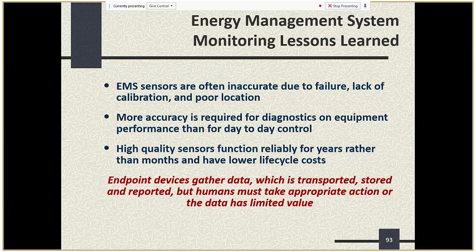Go to slide 94. Yeah, Dave, if I could inject and give an example of this: we actually had a situation with the Wiki lounge on Inter Island Terminal, 3rd floor, where our system was showing that we were losing the fan systems and the ability to control space temperature every afternoon from about 1 o'clock to 5 o'clock.